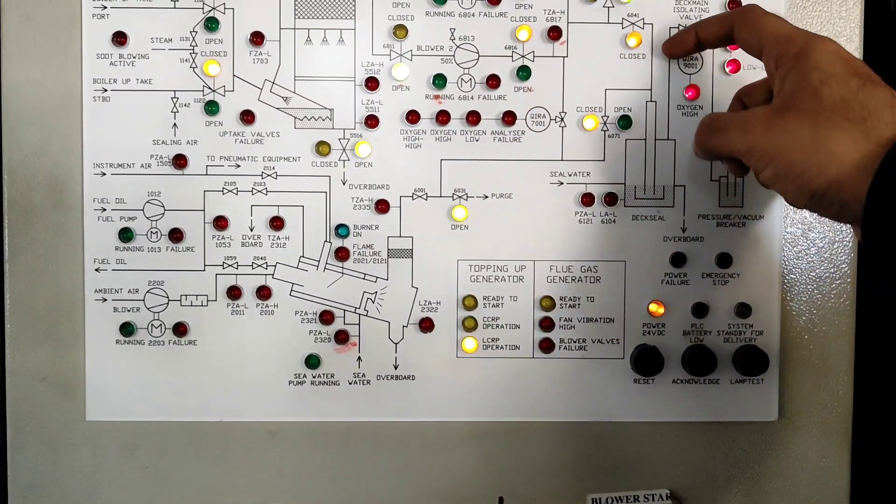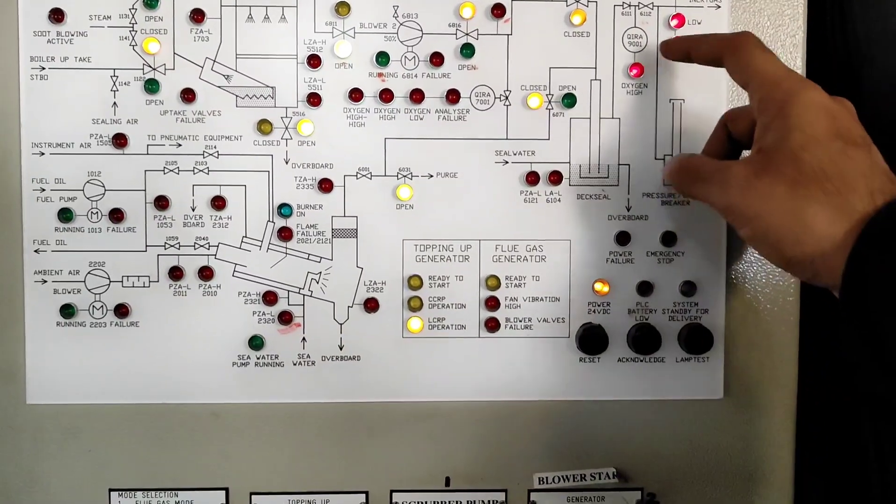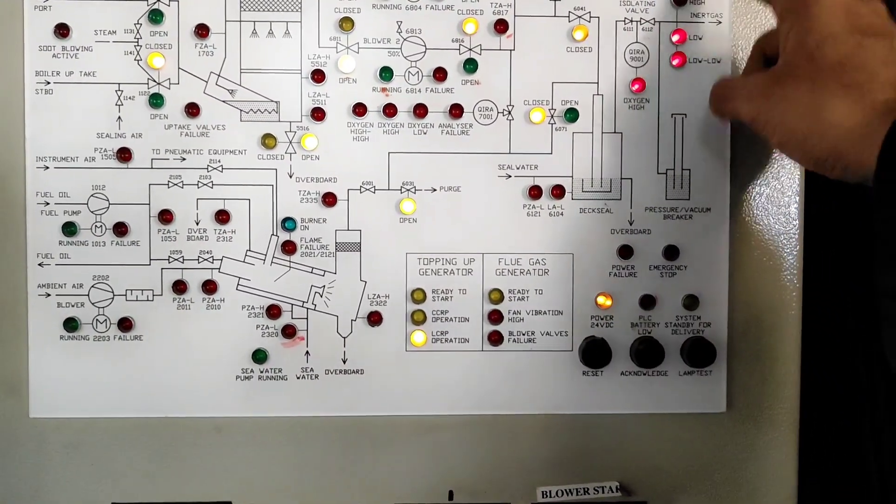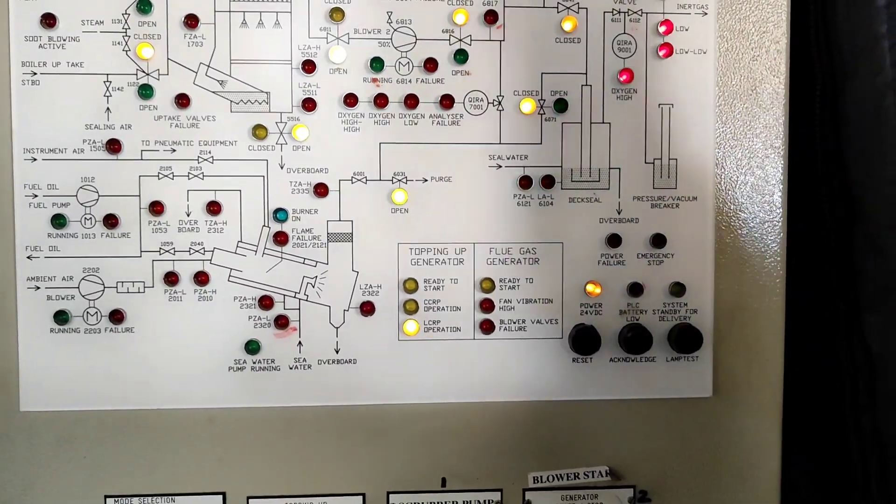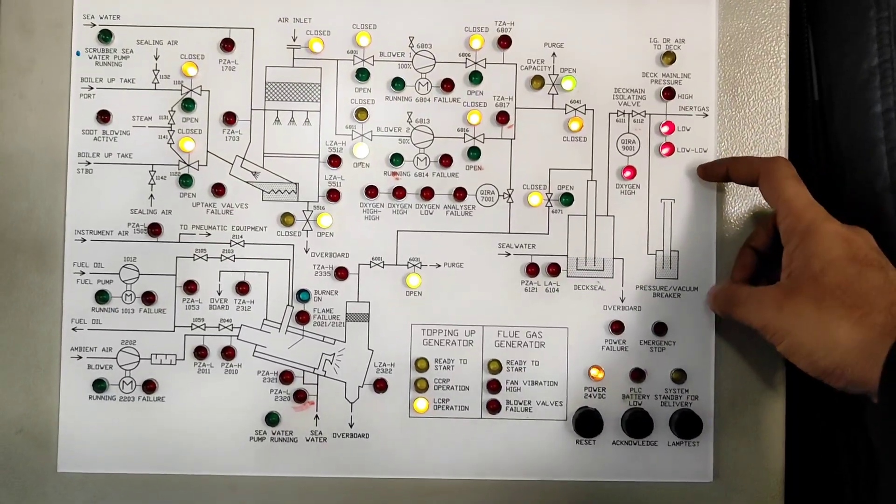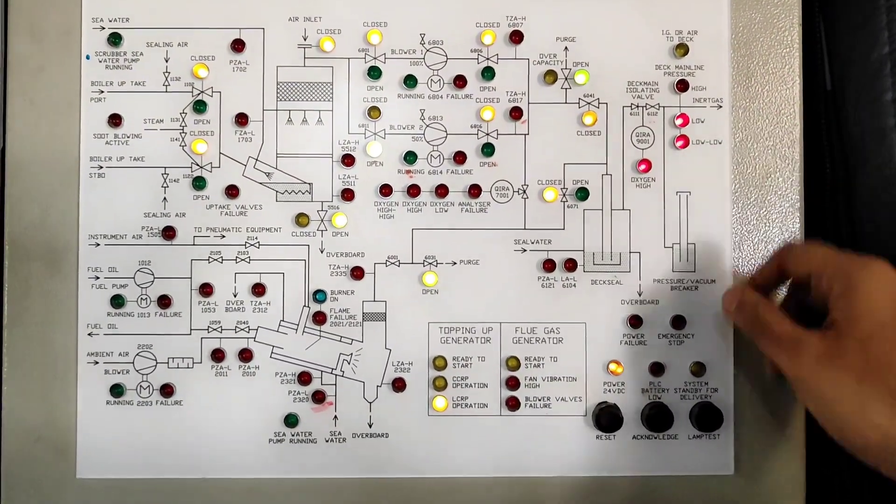So this will open, it will go to deck seal. From here there is a water seal. From here it will come and it is like a deck isolating valve, manual valve. Here oxygen content will also be monitored and then it will go to deck main line where individual tanks will be topped up. So if there is high or low IG pressure these indications will be there.